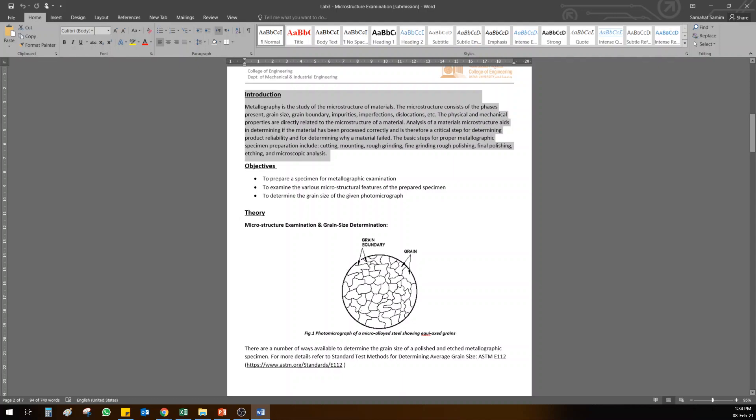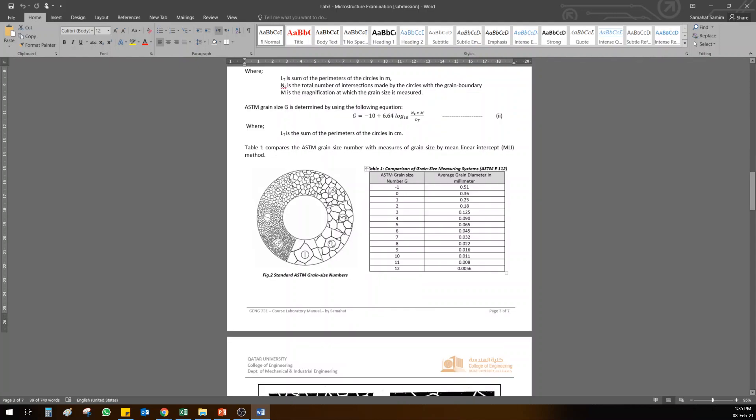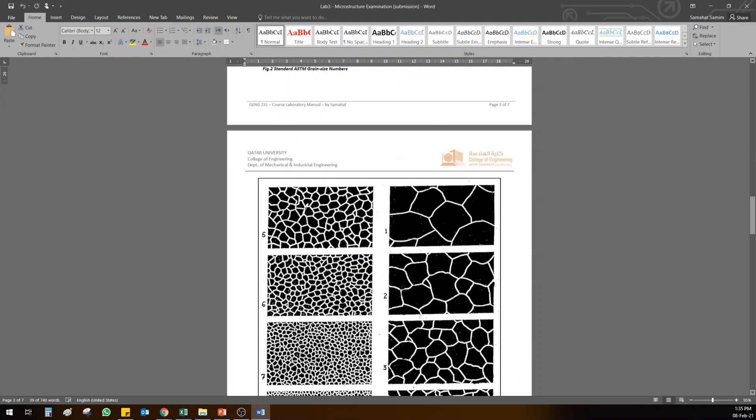It gives you some theory about the two methods, intercept and direct comparison. Also the table is given, the chart is given, as well as these are zoomed-in pictures of the standard 100 magnification. This is what you will compare with when you have direct comparison method.